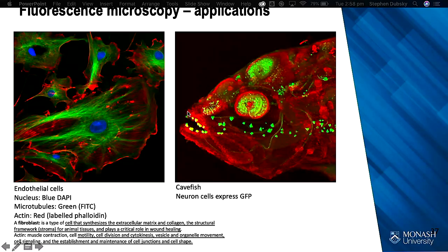This is actually built up as a 3-channel image, and typically each fluorescence is done sequentially. So you'll take the blue, essentially. You'll hit it with a certain wavelength and fluoresce the blue light. You'll image that with a monochrome camera. Then you'll swap your excitation filter and your emission filter, and then you'll get the green and the red, and then you can build a falsely coloured image of those three channels built up together. And I've already shown you this cavefish.